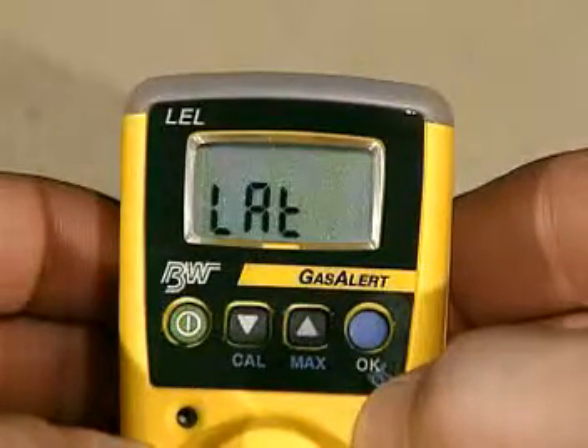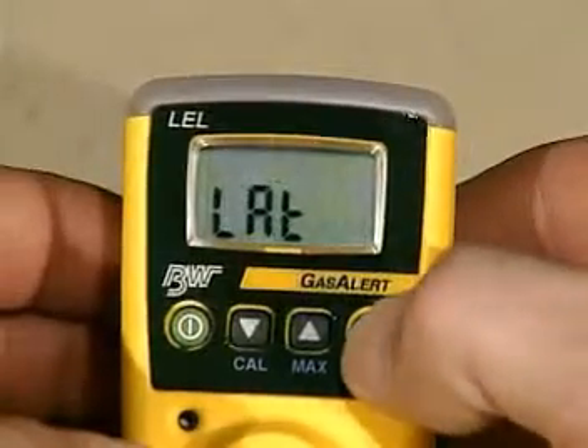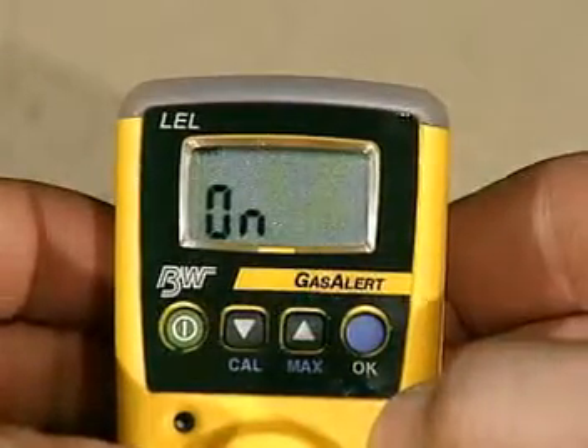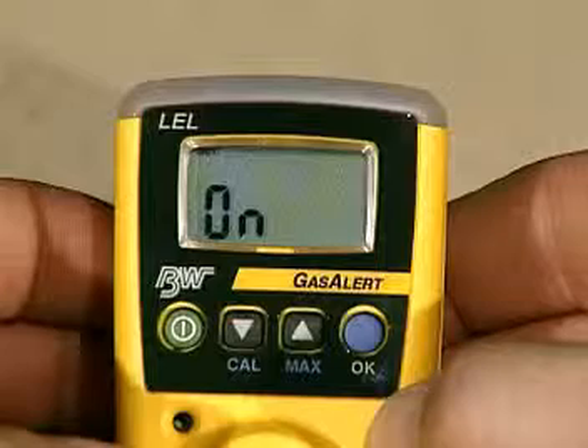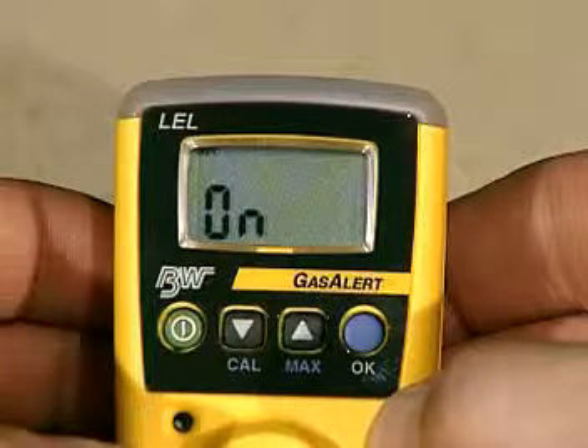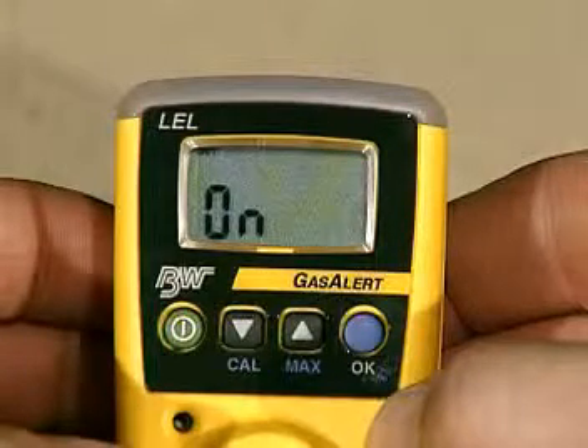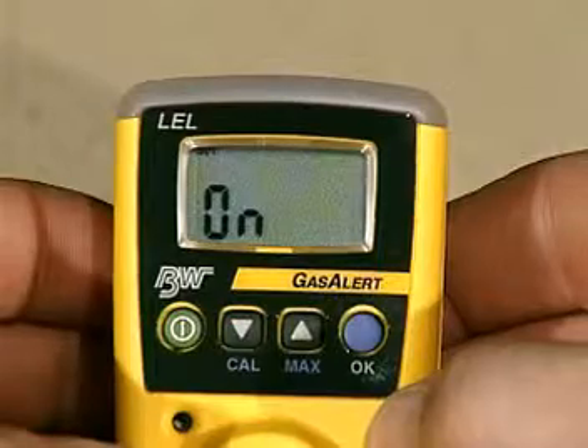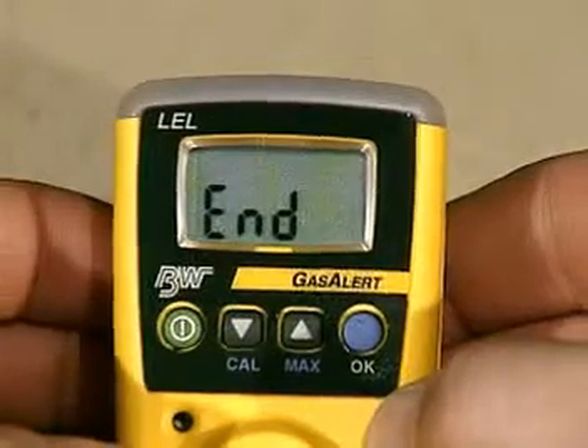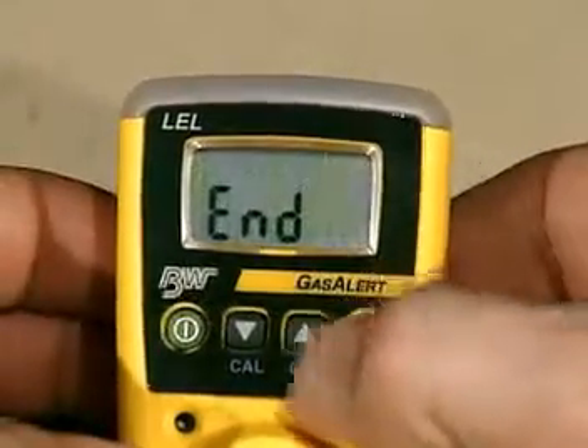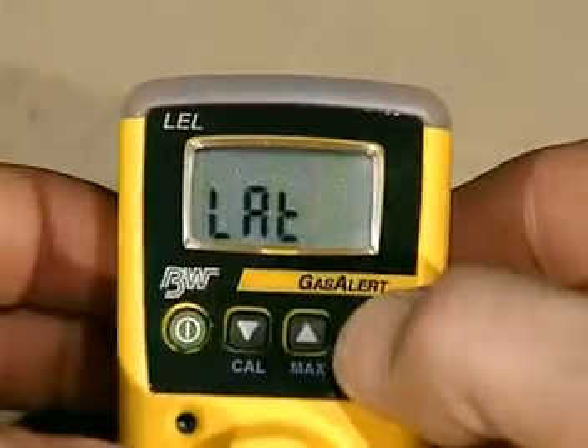Enable the Latching high alarm function by pressing the OK button. The display will read On. The audible visual alarms will now persist until the condition is acknowledged by pressing the OK button. To disable the Latching high alarm function, repeat the sequence. The screen will read Off.